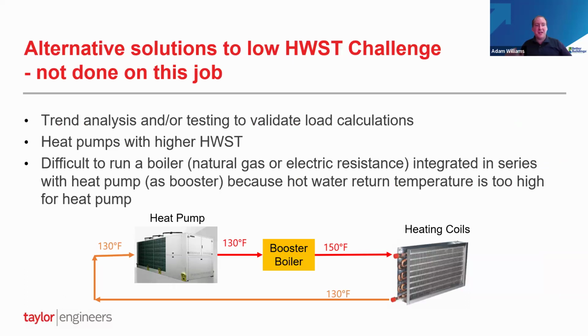So other things that can be done but weren't necessarily done on this job: if you have a system with good controls and trending capability, you can use trend analysis to validate your load calculations. This building, the controls didn't have that functionality and weren't necessarily trusted by all the stakeholders, so we didn't really go that way.